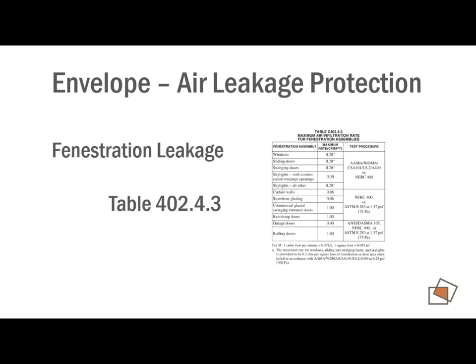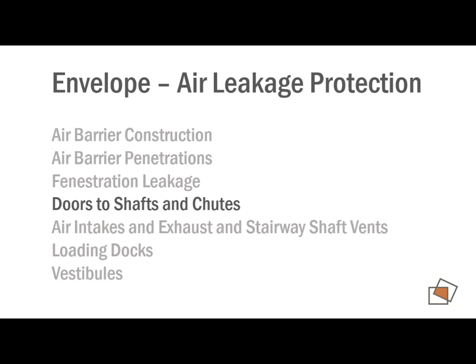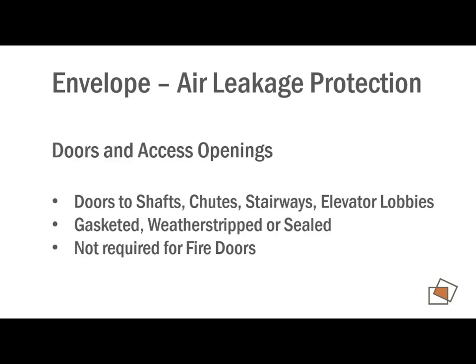So you've got your storefront glazing can only be 0.06 CFM per square foot. And a lot of that's going to be taken care of on the manufacturer side. So it's a matter of you probably specifying these rates, and the manufacturers and the providers of the products are going to need to comply with it. Doors to shafts and chutes, they want you to gasket, doors and stairways, kind of anything that can have a chimney effect in the building and maybe move air through it.